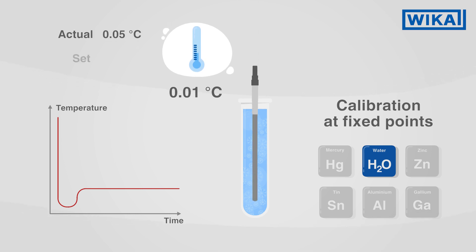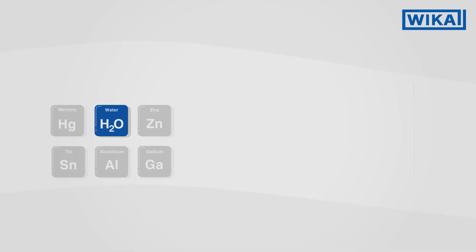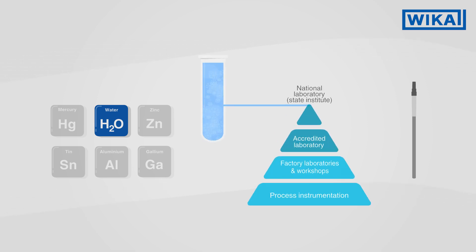On this temperature plateau, the deviation of the test item can now be determined exactly. The fixed point method is suitable for thermometers that must meet high demands for reproducibility and accuracy, and which will themselves be used to some degree as reference thermometers.